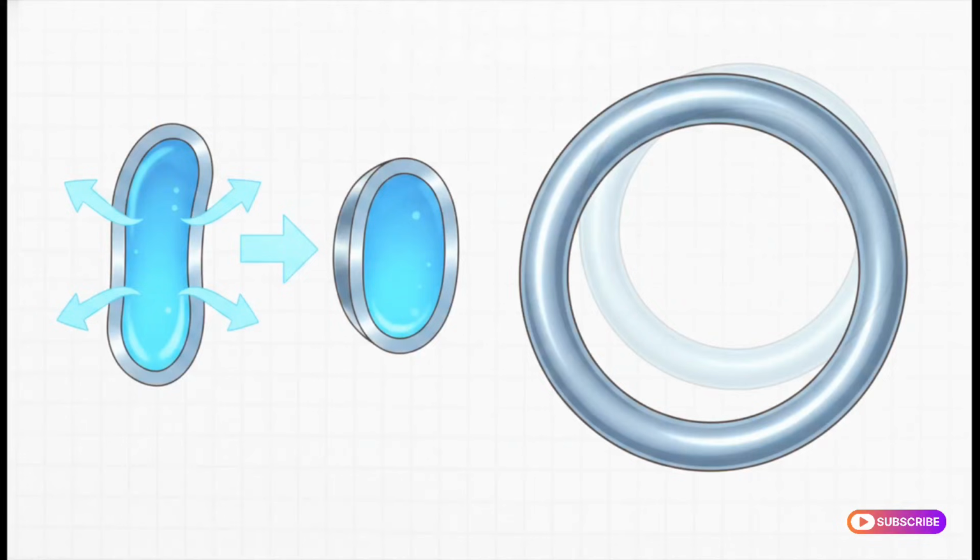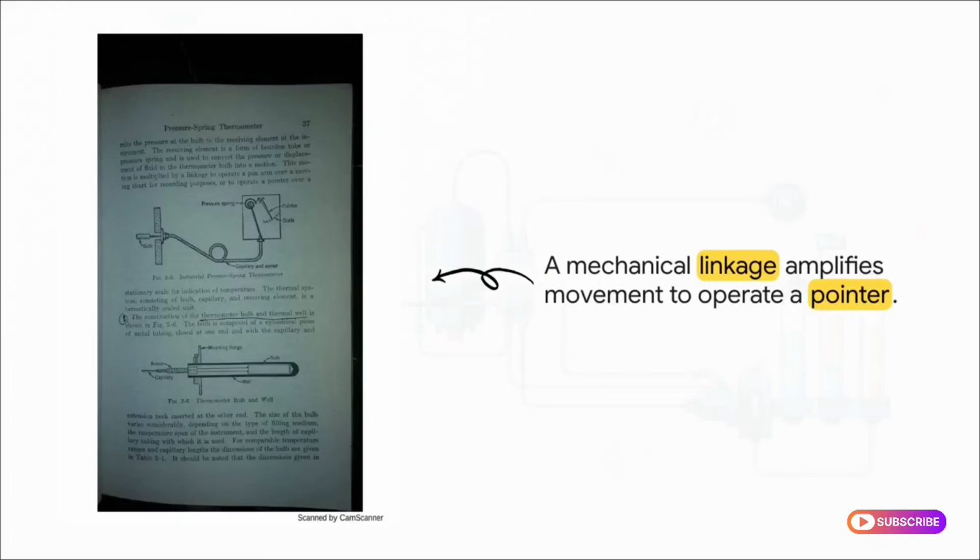The crucial takeaway here is that these aren't just random, curly shapes. They're actually made of metal tubes with a very specific, flattened, elliptical cross-section. When pressure from a fluid or a gas builds up inside them, that elliptical shape desperately wants to become completely round. And as it tries to round out, the entire coil literally uncoils and straightens out. It acts as a mechanical amplifier, taking just a tiny amount of internal pressure and turning it into a very useful, visible, physical motion.